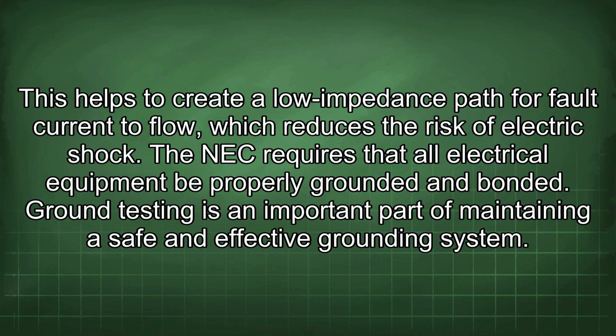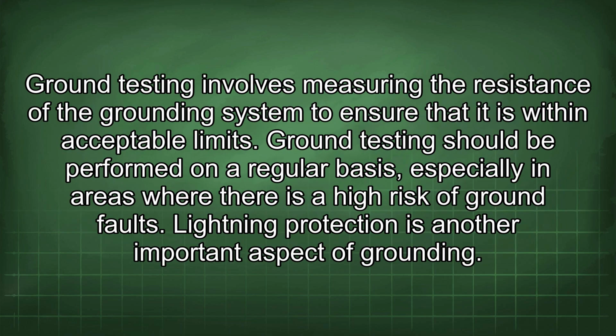Ground testing is an important part of maintaining a safe and effective grounding system. Ground testing involves measuring the resistance of the grounding system to ensure that it is within acceptable limits. Ground testing should be performed on a regular basis, especially in areas where there is a high risk of ground faults. Lightning protection is another important aspect of grounding.